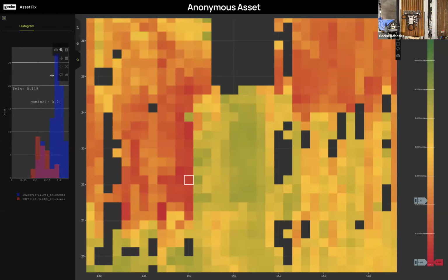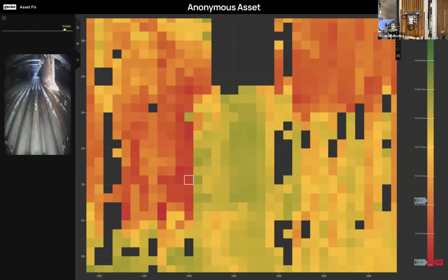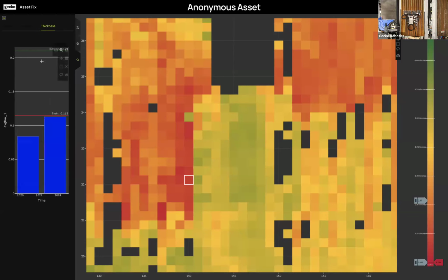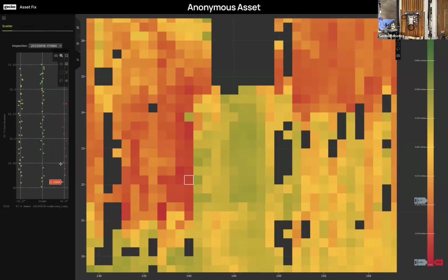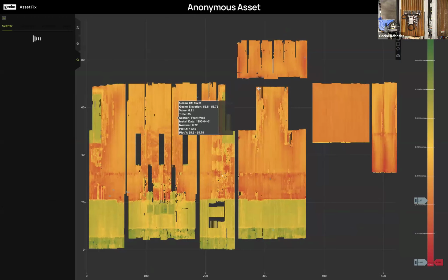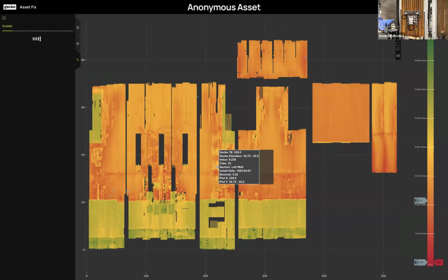So that gives us a window into how that tube is responding in the environment that it's in. It's not necessarily that the whole tube is wearing away at an even rate, but by double clicking and getting very granular, we can see if it's left, center, or right within a 3-inch bin. That's right. Wow. Okay, so that's taking us really deep into the 100 readings that are inside this 3-inch area. When we wrap that all into bins like this, we're left with about 100,000 of these 3-inch areas covering the whole boiler.